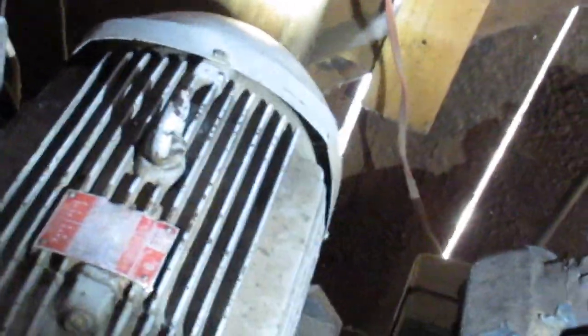Okay, let me fix this. Don't pay no attention to my wiring — it might be a little crude, but it works. That box there is the starter box. Let me flip it on — Mother's going to flip it. See, it can start up, but it never comes up to speed, and it throws this breaker.